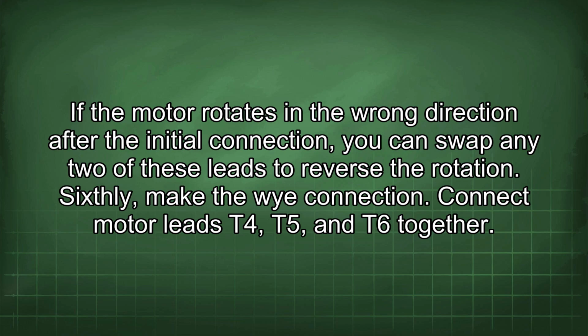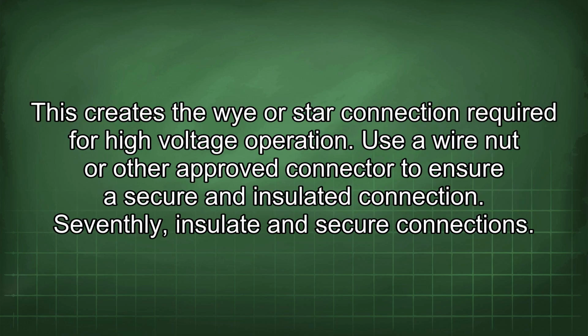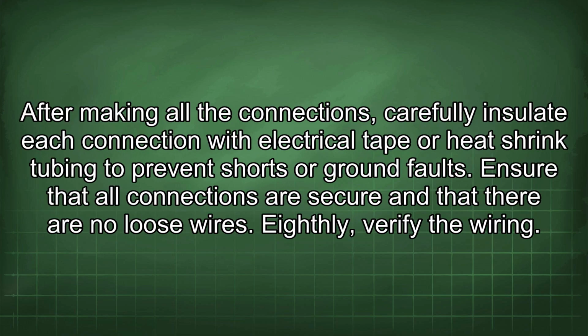Connect motor leads T4, T5, and T6 together. This creates the Y or star connection required for high voltage operation. Use a wire nut or other approved connector to ensure a secure and insulated connection. Seventhly, insulate and secure connections. After making all the connections, carefully insulate each connection with electrical tape or heat shrink tubing to prevent shorts or ground faults. Ensure that all connections are secure and that there are no loose wires.